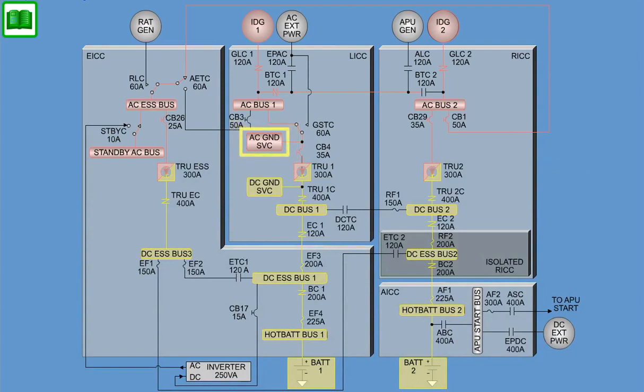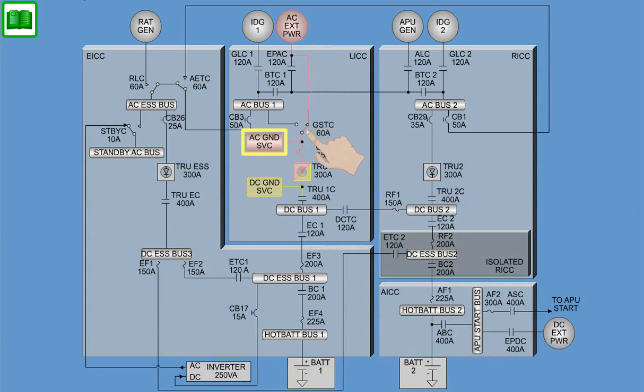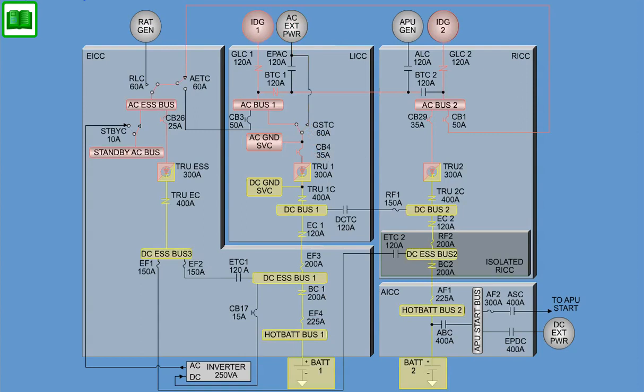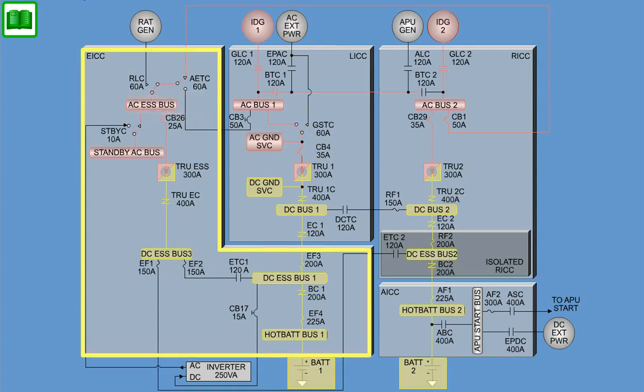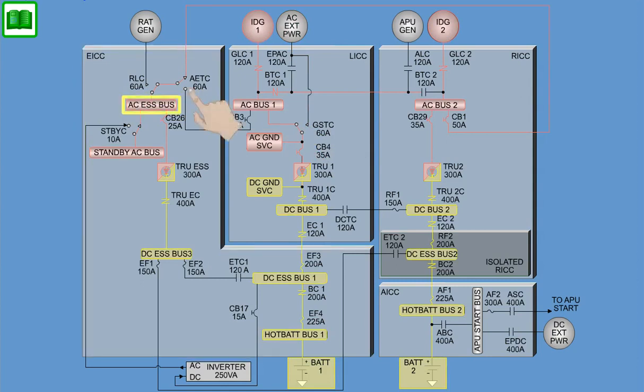The AC ground service bus is supplied out of AC bus 1 or external AC source through the ground service tie contactor. The AC essential bus, located in the emergency integrated control center, is supplied through the alternating current essential tie contactor. The standby AC bus is supplied out of the AC essential bus through the standby contactor. AC bus 1, or the AC ground service bus, supplies transformer rectifier unit 1. AC bus 2 supplies TRU2, and the AC essential bus supplies essential TRU.